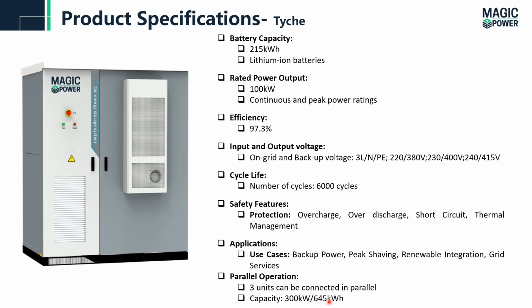The next one is the medium scale energy storage system. The series is called Tyche, and the battery capacity is 215 kilowatt hour. Cell technology is lithium ion. Rated output power of the system is 100 kilowatt, which is a continuous and peak power rating. Efficiency of the system is 97.3. For voltage, input or output, again the system is three phase, so it could be 380, 400, or 415. The life cycle of the battery is 6,000. Safety features on the battery side: overcharging and over-discharging. On the load side: short circuit, overloading, or overcurrent. For the system itself, there is thermal management. Applications or use cases are again backup power, peak shaving, renewable integration, and grid services.